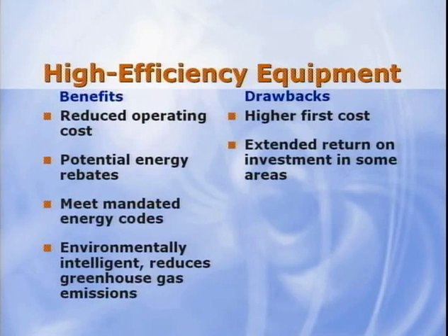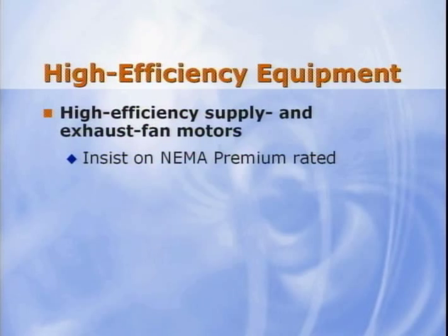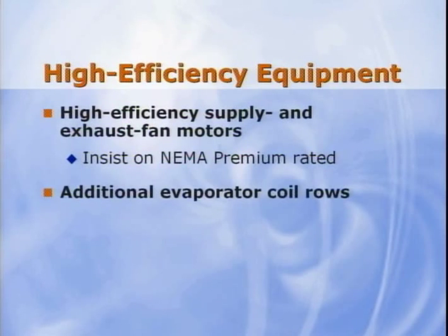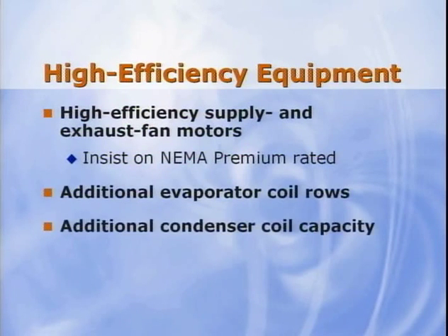There are several options available with packaged rooftop units that lend themselves easily to designing a more energy efficient application. High efficiency supply and relief motors, additional evaporator coil rows, and condenser coil capacity. These optional features can incrementally increase the unit's energy efficiency over applications utilizing standard coils and motors. Additional evaporator and condenser coil capacity can also provide incremental unit capacity.